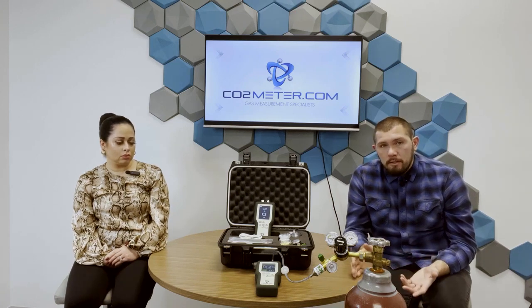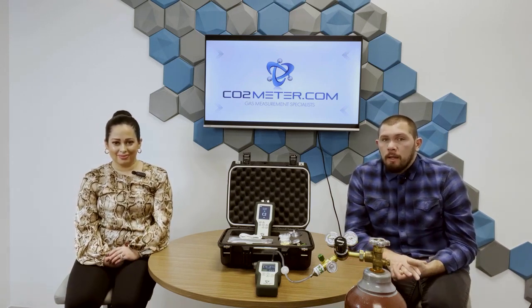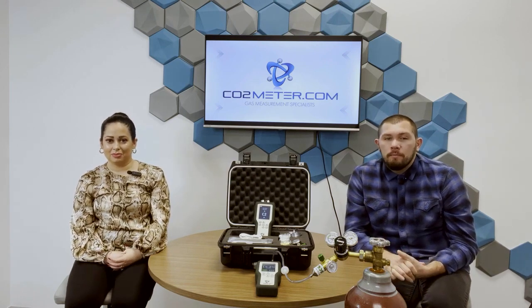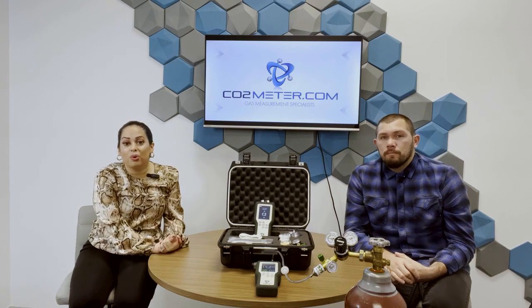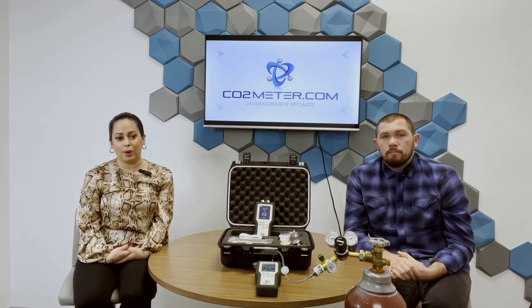Just make sure that you secure a true calibration gas mixture. Someone like Linde would be a great source to get a certified calibration gas to do that. The other part of making sure that you're doing that calibration correctly is making sure that you follow the procedure that we've published to a T. That way your device is performing optimally. If there are any questions that come along the way while you're calibrating, make sure that you contact us. We do have live support, able to get on the phone with you and make sure that you're doing that calibration correctly. Absolutely. Also, for another reference point, we will have a manual included with each device. There will be a troubleshooting guide and a specific section for calibration that you can always reference, which I think is super helpful as well.